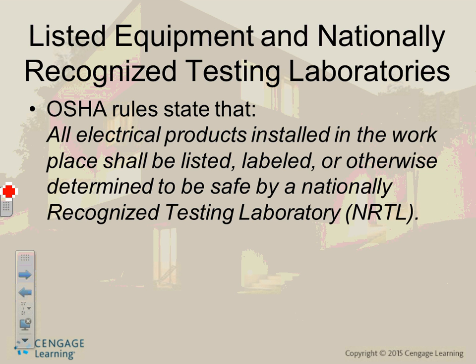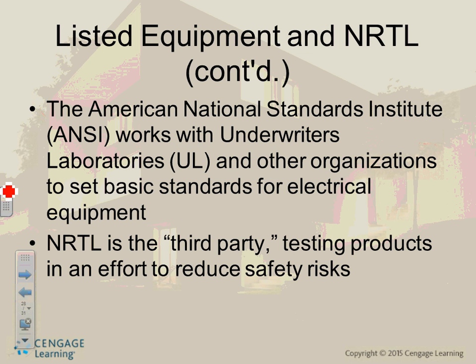OSHA requires all electrical equipment that you use to be installed, and it has to be listed and labeled. It's the law. That's why the coffee can cannot be installed - not because it's not creative, but you have to go to UL and get it listed and labeled, and guess what, it costs you an arm and a leg to go through the testing and labeling too. So OSHA, which is Minnesota OSHA and federal OSHA, the law of the land, forces you to list the equipment and label it. This is a big deal, guys.